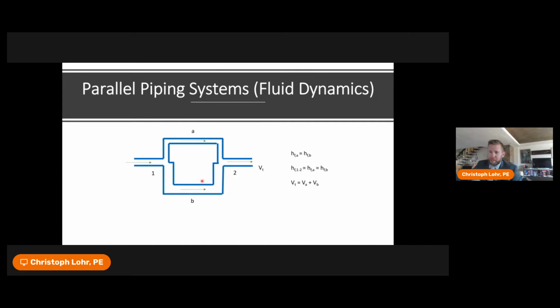Now, the next question I typically ask is, well, what is the volumetric flow rate of A versus B? Most engineers understand right off the bat that the flow rate through B is greater than A because that's the path of least resistance. Again, there's less of a pressure drop through B. The next question I ask is, how do you get more water flowing through A? It takes a little bit longer, but the answer is you increase the pressure drop through B.